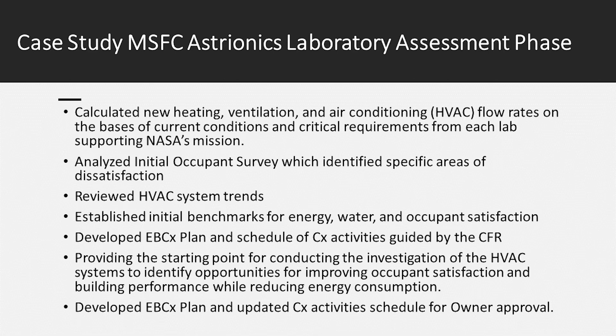As part of the scope of work, we did the calculations and determined the loads. First we had TAB go out and do actual readings to figure out what they were getting as far as outside air, and what was being delivered in total on the units as far as the air handler goes.